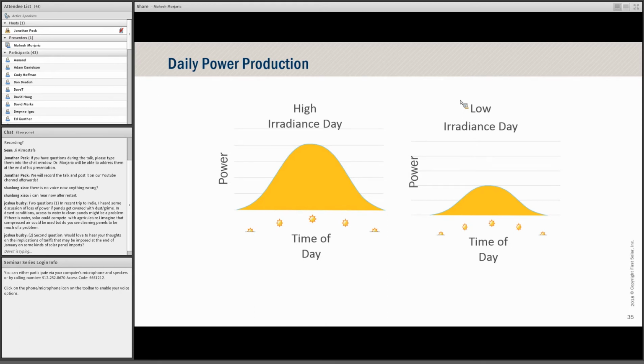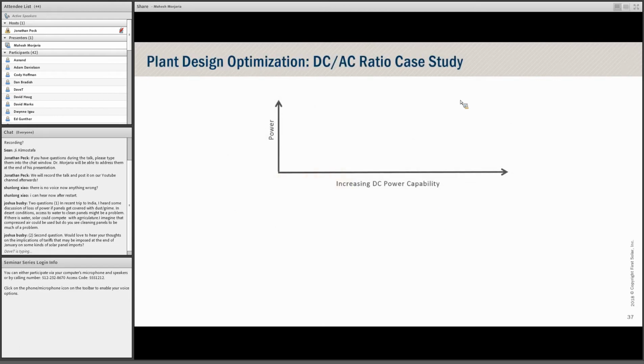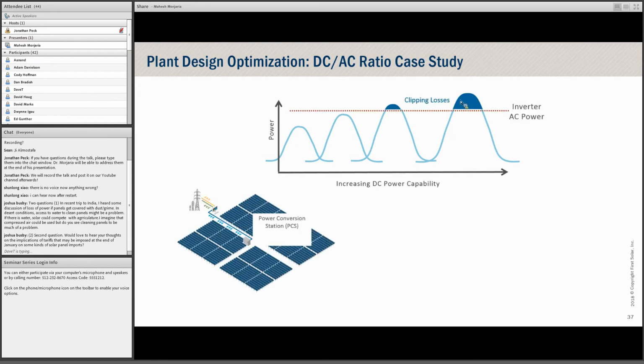So how do you design this in a way that optimizes the output of the plant over the whole year? The way we do that is by increasing the DC power capacity. For the same amount of AC, if we keep increasing the DC power, it acts like increasing the irradiance, or for the same irradiance, it's increasing the power, as shown schematically here.